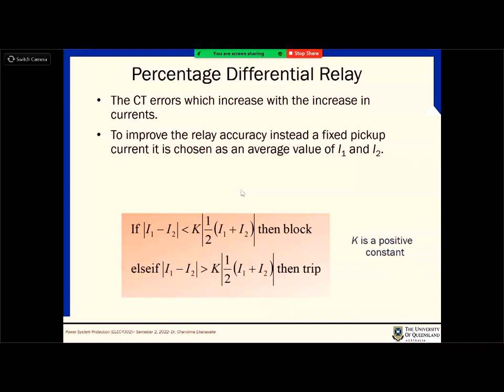And one of the reasons for this is the errors associated with the CTs, because all the CTs are not 100% correct, right? If you are going for very small differential scheme values, then that may be introduced by the relay errors, the CT errors, not by the real fault, right? So to avoid all those issues, we can go for this one. So the pickup is not a constant, it changes with the load conditions.